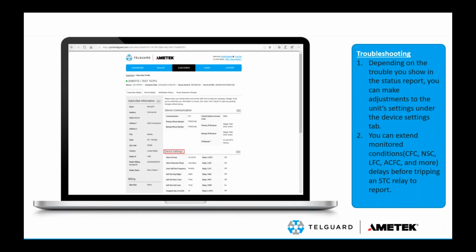Relay 2 is still used, but less commonly for fire because it is a normally closed relay. So as you know, if it's a normally closed relay, we would need a normally closed output or zone to connect it to. Anyone that installs fire, typically we know that fire is normally open.